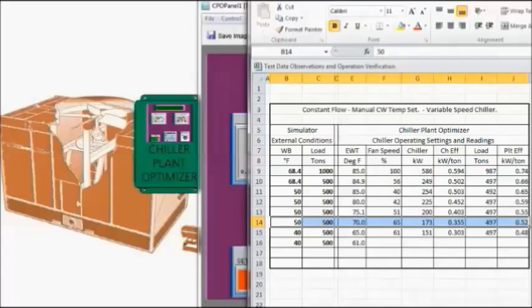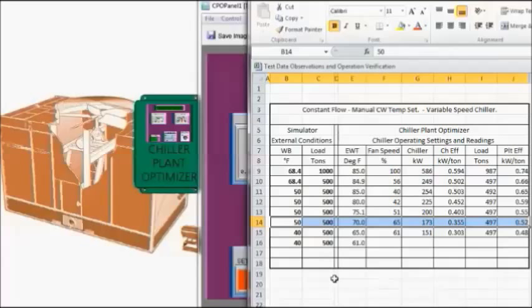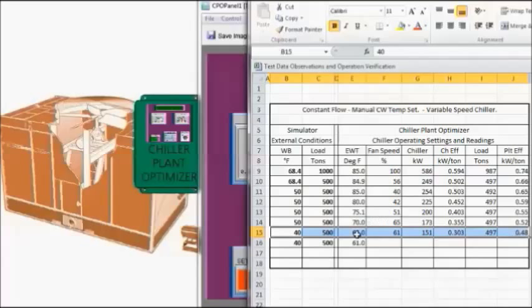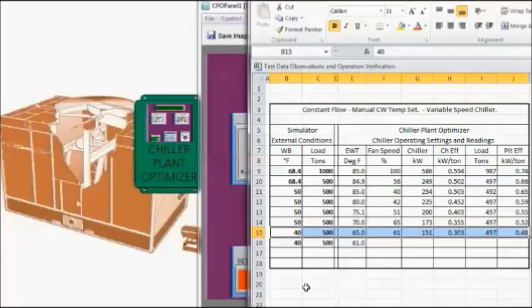So I ran through two more scenarios and I dropped the entering condenser water temperature to 70 degrees. And we got a reduction in chiller efficiency to 0.355 and a plant efficiency of 0.52. So not a big change in plant efficiency. And then I went ahead and dropped the entering condenser water temperature to 65 degrees. I also dropped the wet bulb to 40 degrees because I didn't want to get into something called cooling tower relief at this point. I'll explain cooling tower relief in my next video.